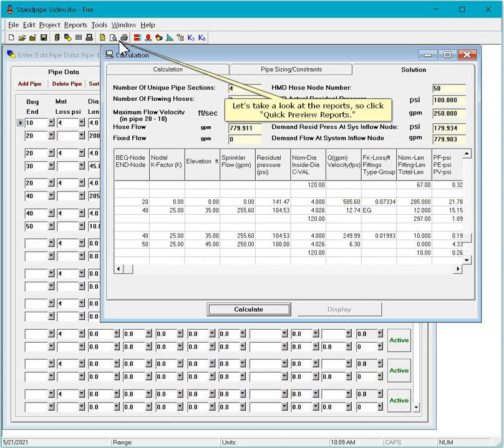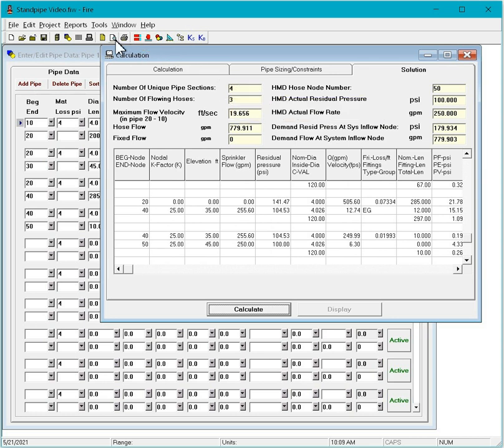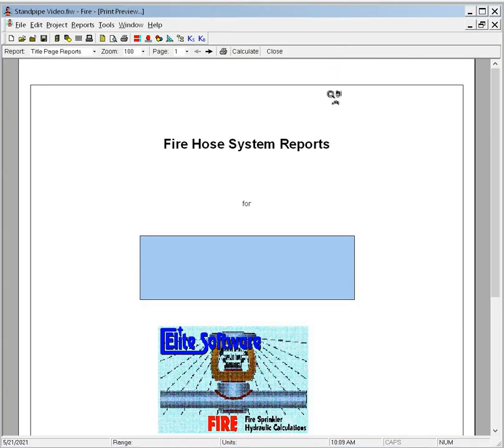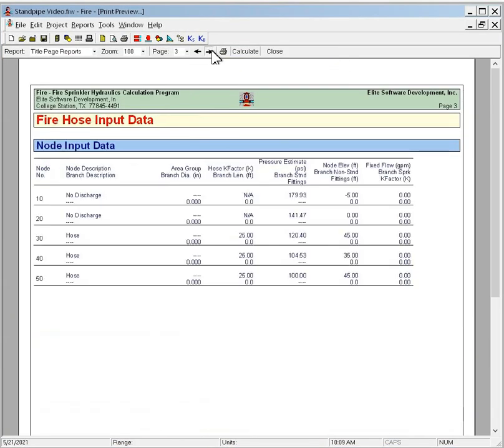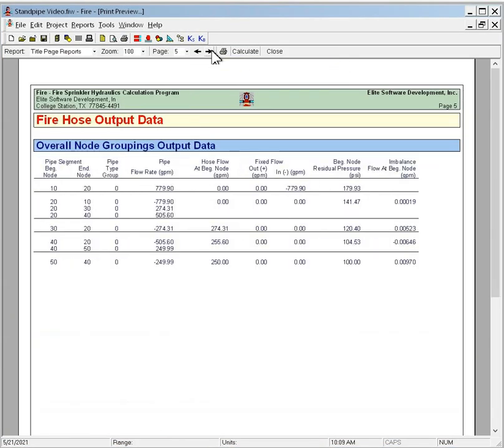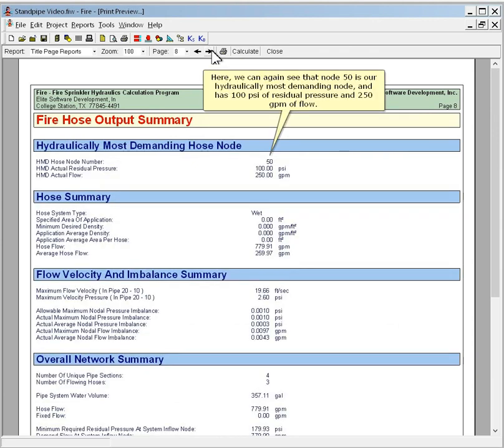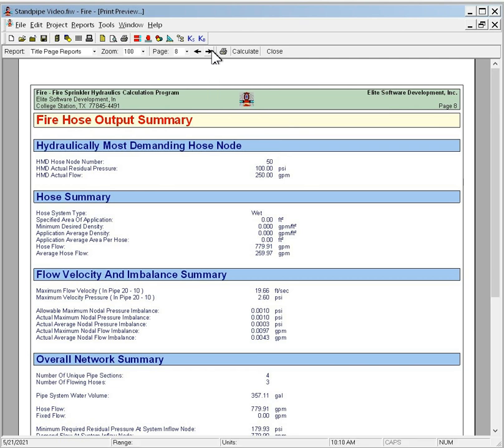Let's take a look at the reports, so click Quick Preview Reports. Here we can again see that node 50 is our hydraulically most demanding node, and has 100 PSI of residual pressure and 250 GPM of flow.